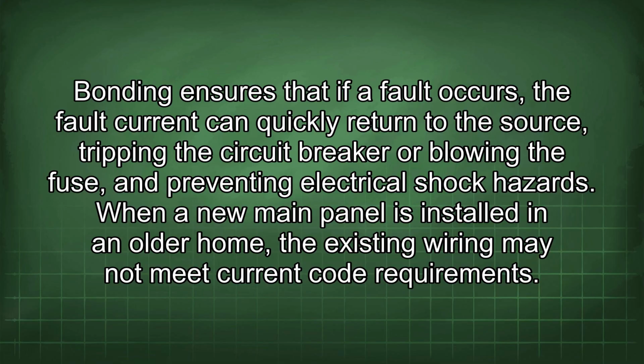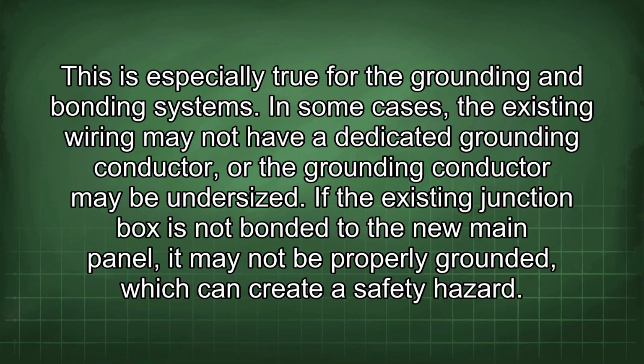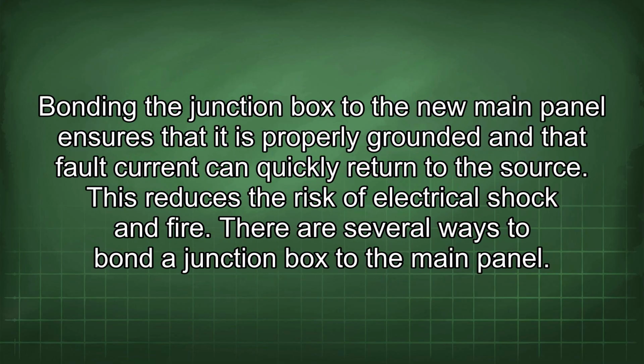When a new main panel is installed in an older home, the existing wiring may not meet current code requirements. This is especially true for the grounding and bonding systems. In some cases, the existing wiring may not have a dedicated grounding conductor, or the grounding conductor may be undersized. If the existing junction box is not bonded to the new main panel, it may not be properly grounded, which can create a safety hazard. Bonding the junction box to the new main panel ensures that it is properly grounded and that fault current can quickly return to the source. This reduces the risk of electrical shock and fire.